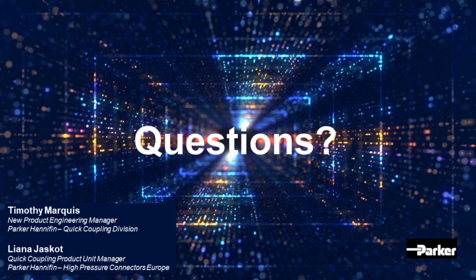I'd say too, if we're talking about connecting multiple lines, connecting the inlet and outlet at the same time - that's what we do a lot of times with blind mate couplings as well. As you connect a system together, you blind mate multiple connections at the same time, set up as part of the IT gear typically, or a different manifold setup depending on the exact application. But it is something we have offered in a lot of solutions, a lot of different applications as well.